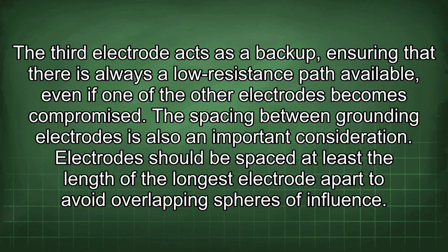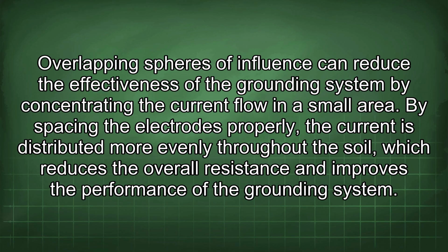The spacing between grounding electrodes is also an important consideration. Electrodes should be spaced at least the length of the longest electrode apart to avoid overlapping spheres of influence. Overlapping spheres of influence can reduce the effectiveness of the grounding system by concentrating the current flow in a small area. By spacing the electrodes properly, the current is distributed more evenly throughout the soil, which reduces the overall resistance and improves the performance of the grounding system.